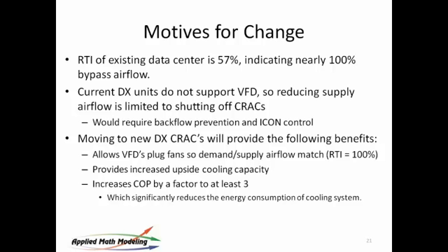And nowadays, VFD does not mean chilled water, because Liebert and others, APC and others, are now building variable speed direct expansion cooling units. So you can replace them, but you can't always adapt the DX unit with a VFD. You can do a little of that, but only if you know what you're doing.